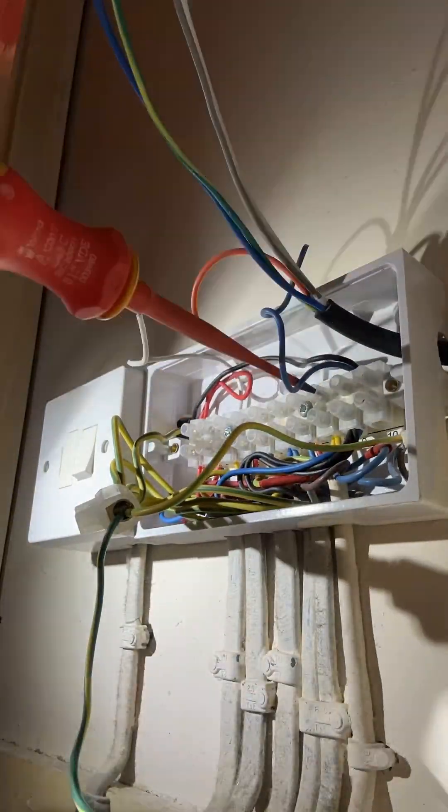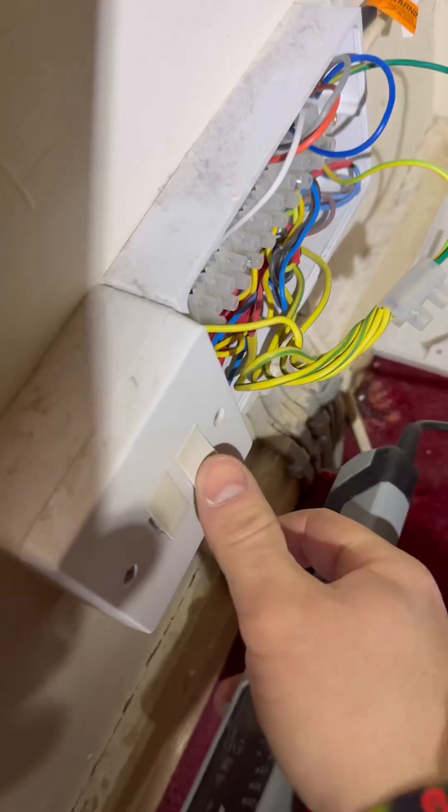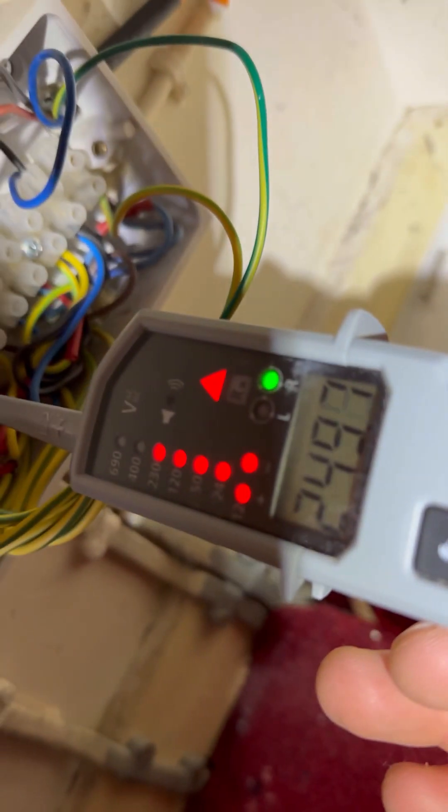It doesn't matter how confident you are with wiring, I still think the best technique to wire a valve like for like is just do cable at a time. That way you can't go wrong and it's wired up then exactly the same as it was before. So we turn the power back on once all that's wired in.